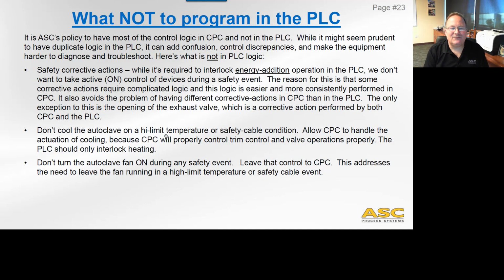The reason for this is that some corrective actions require complicated logic, and this logic is much easier and more consistently performed in CPC. It also avoids the problem of having different corrective actions in CPC than in the PLC. So we don't have to try to be harmonized in terms of which one's taking control. We're going to say CPC is going to take control in these cases. The only exception to this, there's one exception, and that is the PLC will open the exhaust valve. And that is a very simple action, and we've determined that the PLC can do that. And that is the only corrective action that we're going to allow both to do, okay?